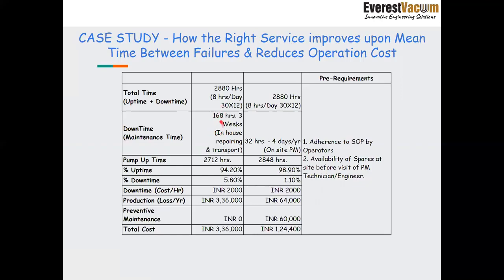Now on the left side is where no preventive maintenance is done. On this side, preventive maintenance has taken place. So the downtime is very high if there is no preventive maintenance, because if the SOP is not followed, there can be certain serious breakdowns, and the breakdowns can go up to 3 weeks. So that is 168 hours of breakdown, because that involves the in-house repairing and the transport as well. Whereas for the preventive maintenance, it is just 4 days per year, that is 32 hours.